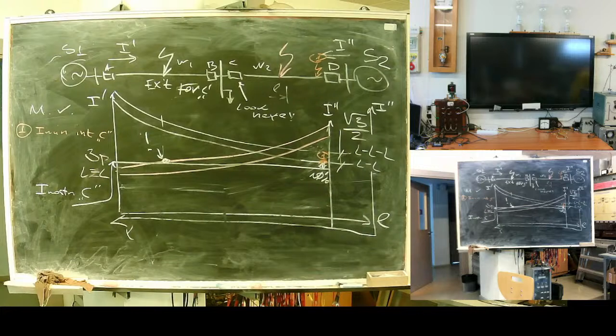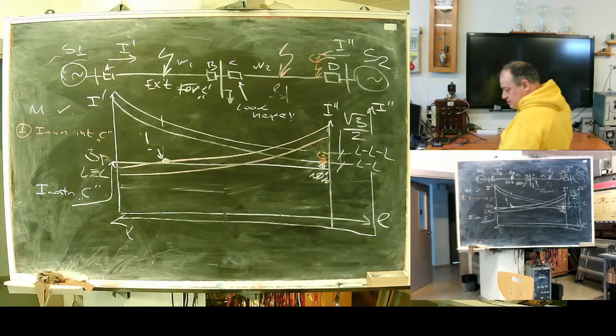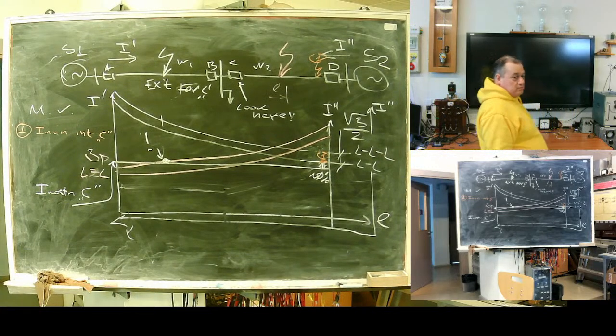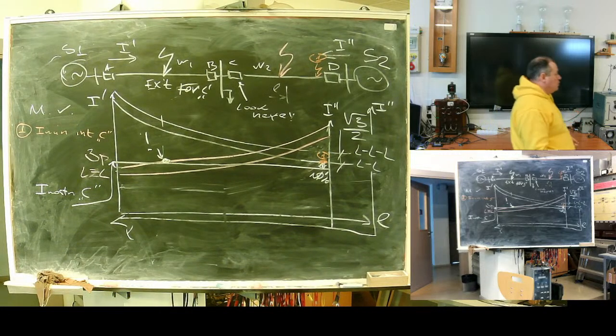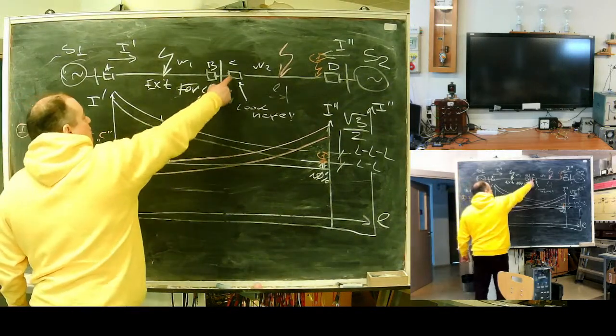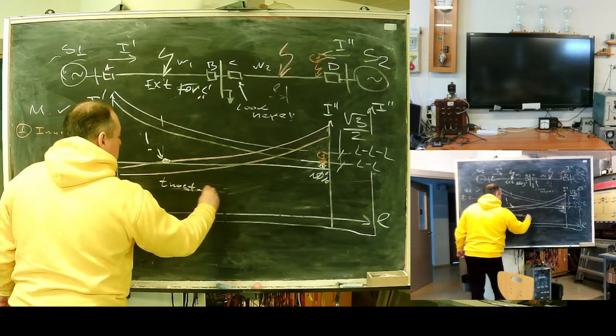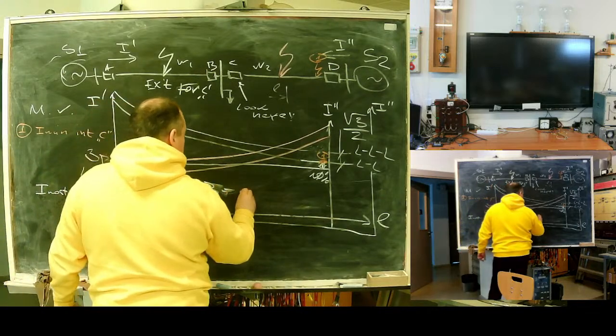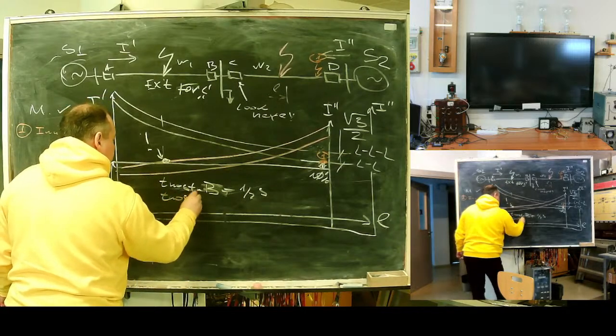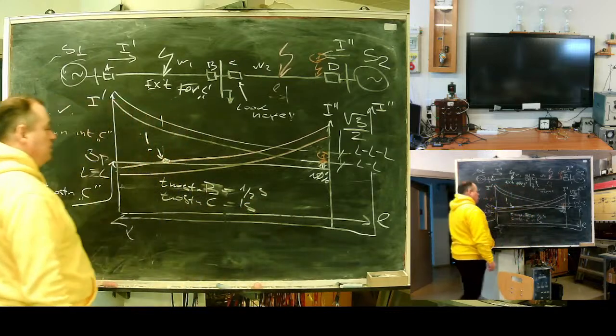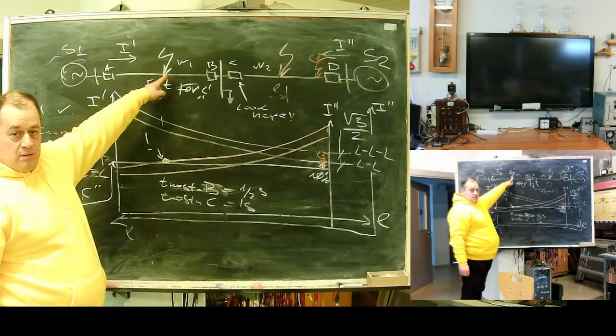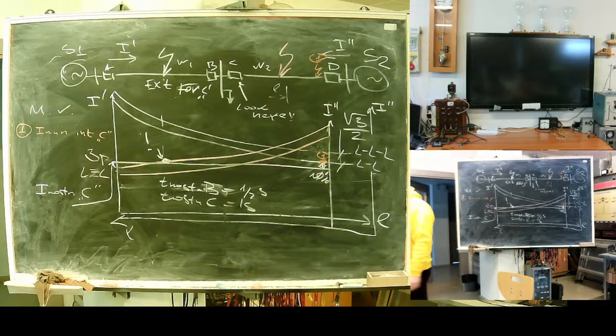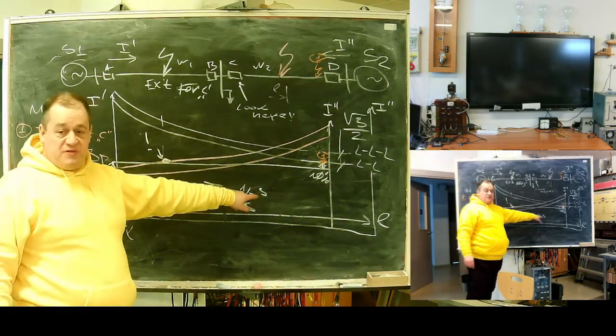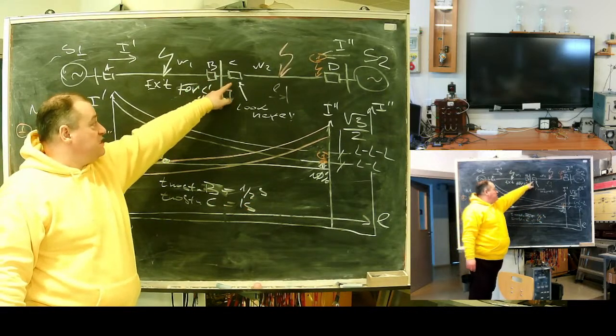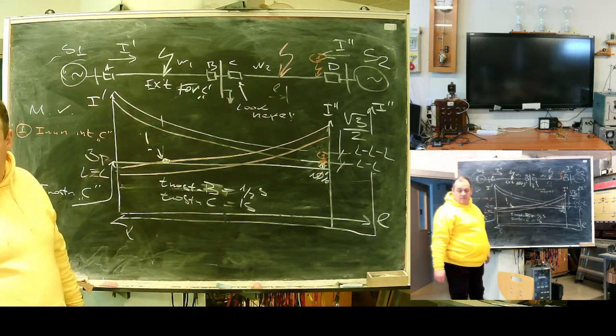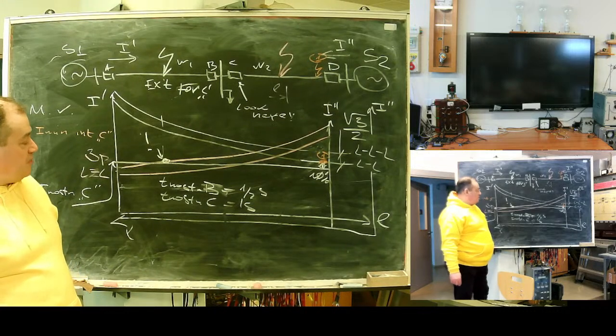What can I do? Ideas. How do we achieve selectivity? It's time delay. Yeah. Okay. Let's say where I have a problem between B and C. Operation time for B should be, let's say, 1/2 second, and for C should be 1 second. Now in case of this fault, what happens? Both B and C start. But B sends the disconnection signal after 1/2 second, this switch disconnects, C returns to its initial state. Agree? Agree. Did I solve the problem?